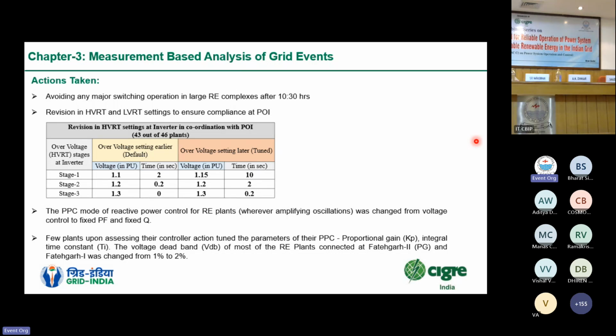We asked those plants to change their mode from the voltage control to constant reactive injection mode or a fixed power factor mode, so that they are not at least amplifying the oscillations during the instability. Another short-term measure we have taken was that we asked certain plants to toggle their deadband so that their voltage controllers are not that sensitive to the voltage variations. In this way, we were able to minimize the oscillation cases. All these measures we mentioned here are just the short-term measures which we took in the operational horizon and achieve somewhat a better power system behavior.